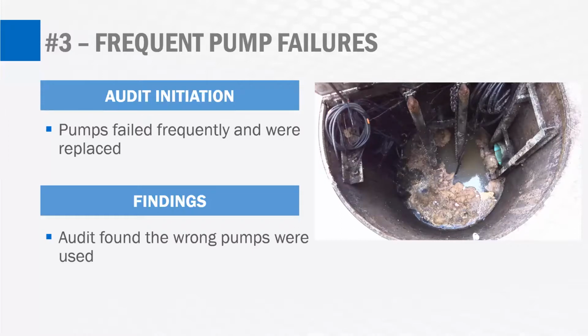There was a slight change in head, similar to what Marco talked about previously, that really threw off where the operating point was on these pump curves. So the audit found that it's best to switch pumps here and utilize a better suited pump that can deal with the varying head conditions and is not going to lead to these pump motors burning up in this situation. Next slide.